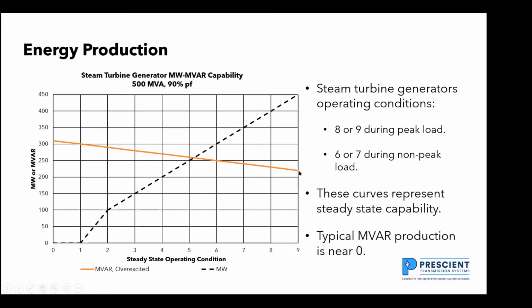The capability is 200, but typically I'm operating the machine down here close to 0 MVAR because the generating people want to operate the most efficient generator they can. And if I'm not pushing MVAR out of the machine, my I squared R losses are lower, and I'm operating close to 0 MVAR on my machine. And that's good because that means I have MVAR capability when a transient occurs.